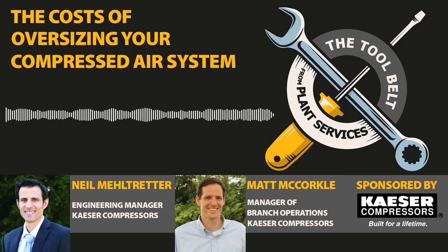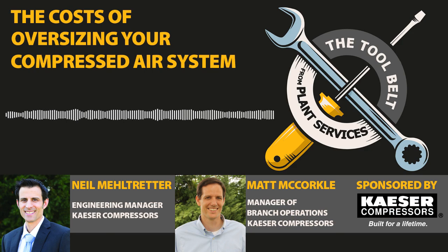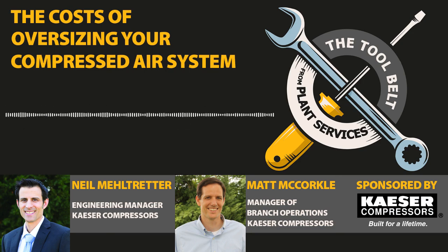Efficiency is really the next key point I'd like to highlight, and we talk about this as a key performance index. Specific power, from an operational or efficiency standpoint, is key, and you can look at that for individual compressors. We have Compressed Air and Gas Institute CAGI data sheets for those, and that tells you what your efficiency is at full load. But again, like Matt said, it's 100% or off, and you don't necessarily know what it is in between.